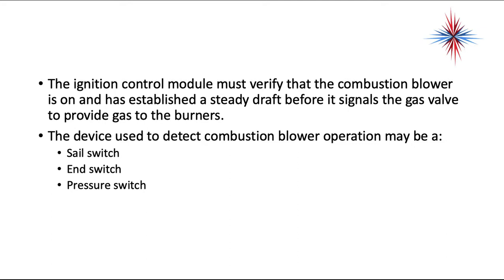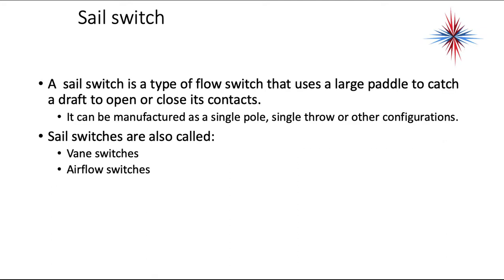The ignition control module must verify that the combustion blower is on and has established a steady draft before it signals the gas valve to provide gas to the burners. The device used to detect combustion blower operation might be a sail switch, an end switch, or a pressure switch.